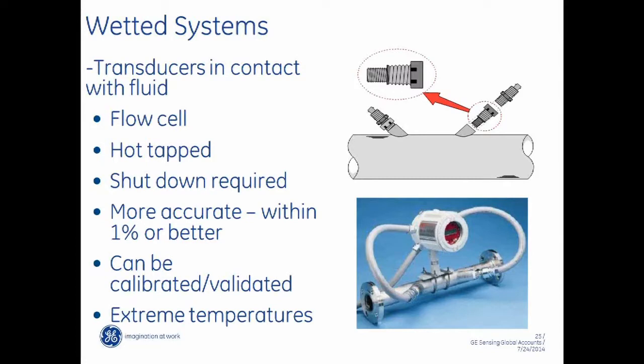The nice thing that I like about this is this piece right here, which is called a pan adapter. It's basically, if you can think of it as a high-end acoustic thermowell. That goes in before the transducer. Here's a plug, and the transducer is behind it. What that does is it isolates us from the process.